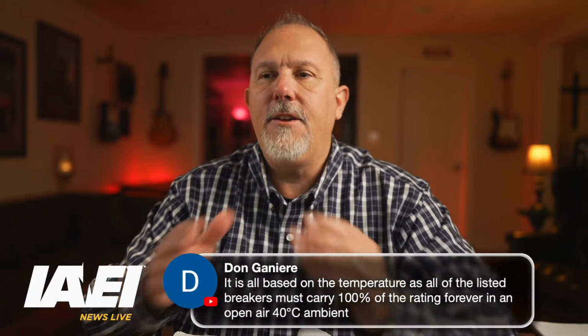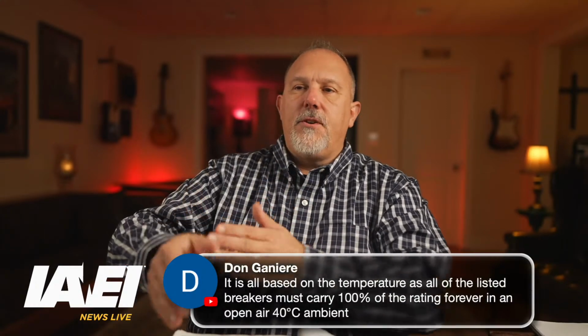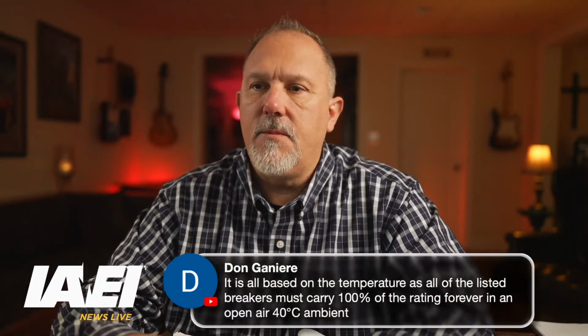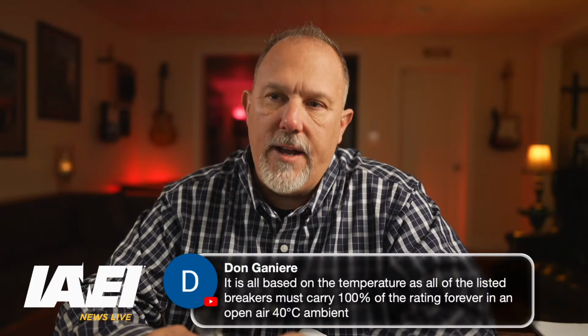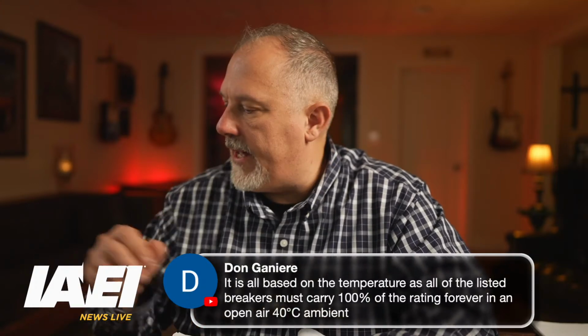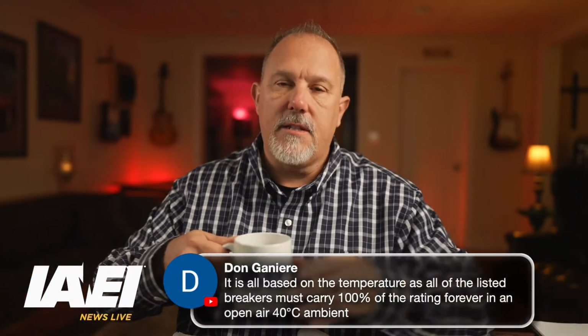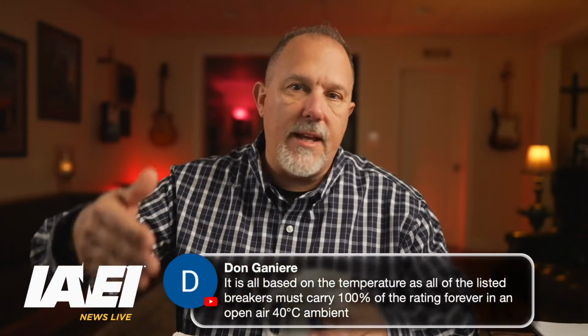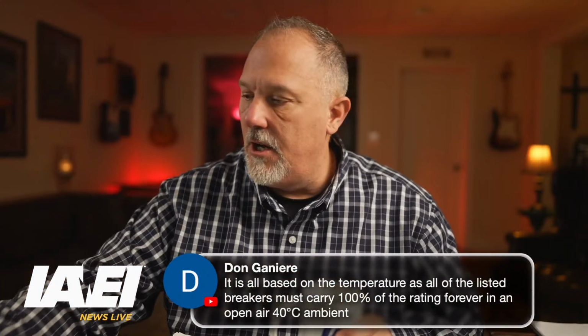And you're right, Don. It's all about the temperature, as all of the listed breakers have to carry 100% of the rating forever in open air 40 degrees C ambient. It's about the temperature rise inside of an enclosure, and I would say that's probably the hardest test for any of the assemblies to have to pass. All right, so I'm going to close out my Acrobat and close out that website.